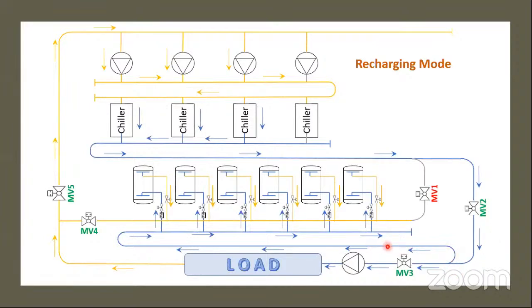For example, if the load is 900 tons and the chillers are 1200 tons, then 900 tons will be sent here, and the 300 tons will be sent here for thermal storage to get charged simultaneously. Once they are charged, the system switches back to the normal mode. So these are the four major modes of operation.